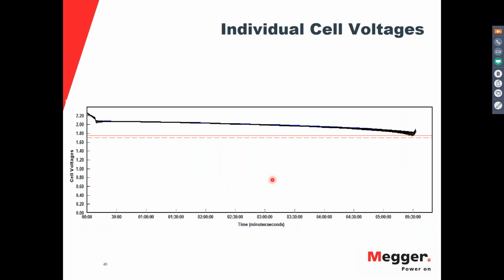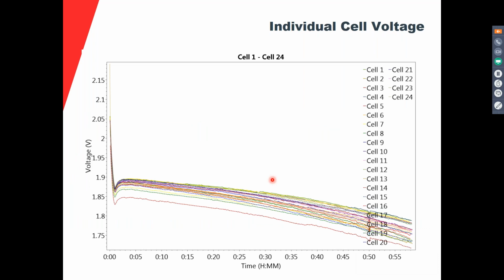Here we see the discharge curve for 24 cells. You can see that there's no variation. All of the cells discharge almost equally, and they have a very similar pattern of discharge. That means that it's a very healthy battery. In this case, we see a little bit of difference, and we start seeing some cells that are deviating, not showing the same pattern. They are discharging faster. Some of them have the same pattern at the beginning, others are totally different from the beginning, and the ones that are the same start deviating throughout the test. So this helps you to determine if there's any problem with individual cells.